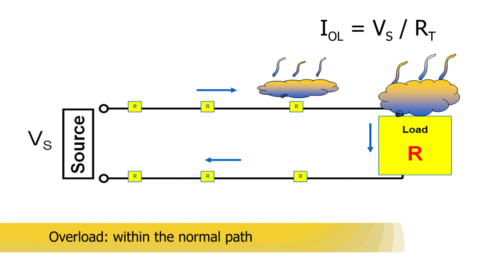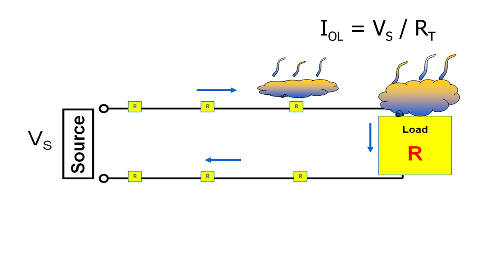Overloads are most often between 135% and 6 times the normal current level. Persistent, non-temporary overloads can result from defective motors with worn bearings or too many loads on a single circuit. It must not be permitted to last long enough to damage electrical system components. This damage may eventually lead to more severe events if the overload is not interrupted. Due to the overload's inherent low magnitude nature, removing them within seconds or even minutes will generally prevent thermal damage. Short circuits differ from overloads as they can be hundreds to thousands of times greater than the normal operating current.